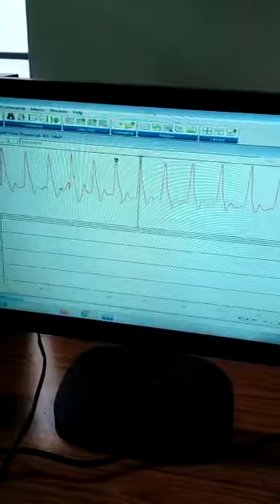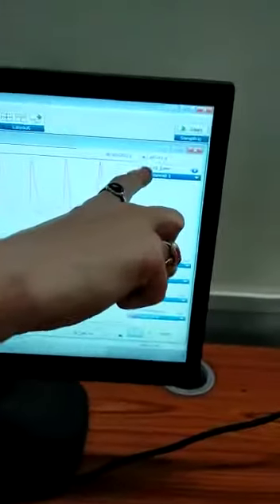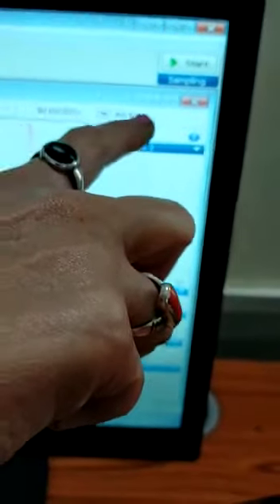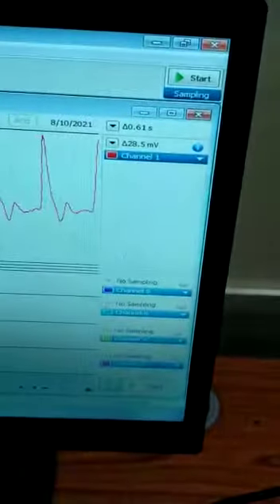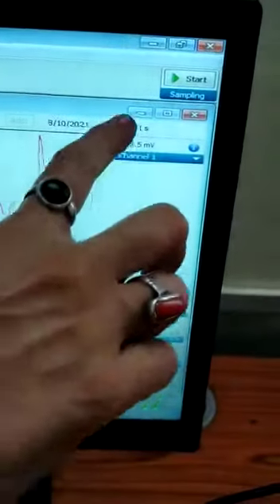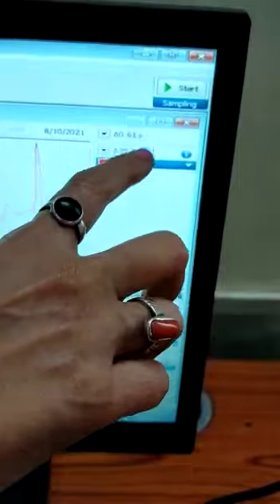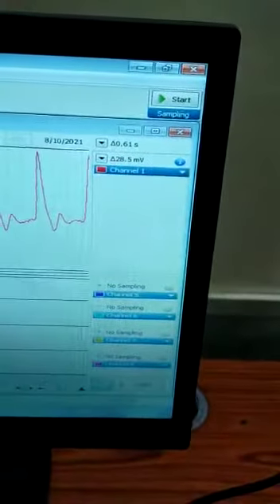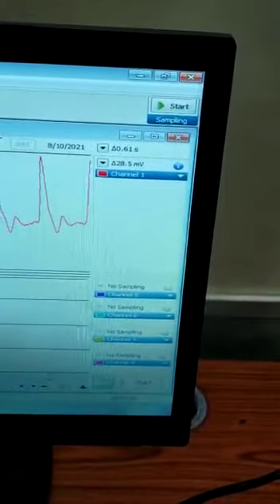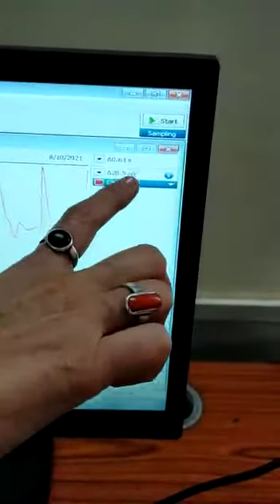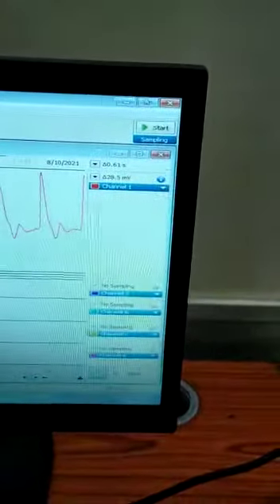For the successive peak, I will set the second marker. This measures delta t, which is 0.61 seconds. You can take this 0.61 seconds for measurement of pulse rate. So 60 divided by 0.61 gives the pulse rate.